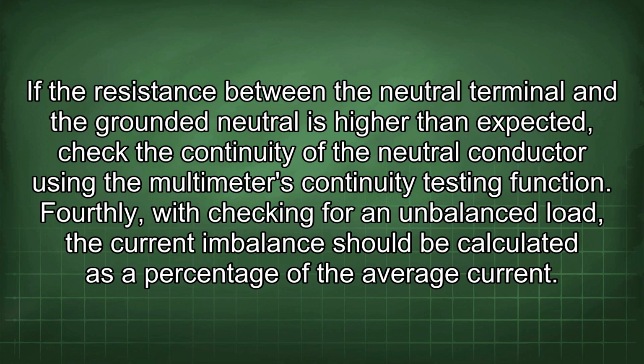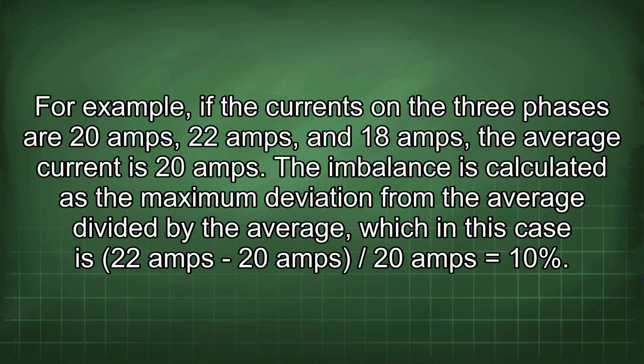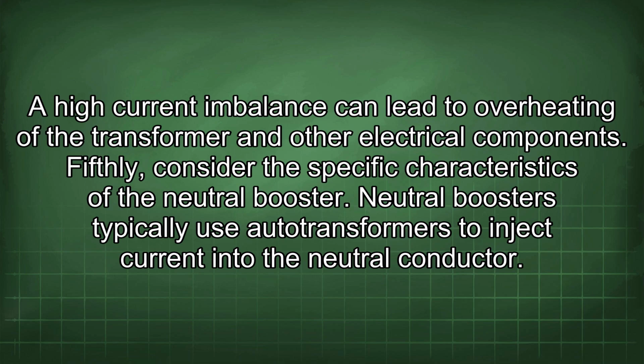Fourthly, with checking for an unbalanced load, the current imbalance should be calculated as a percentage of the average current. For example, if the currents in the three phases are 20 amps, 22 amps, and 18 amps, the average current is 20 amps. The imbalance is calculated as the maximum deviation from the average divided by the average, which in this case is (22 amps - 20 amps) / 20 amps = 10%. A high current imbalance can lead to overheating of the transformer and other electrical components.